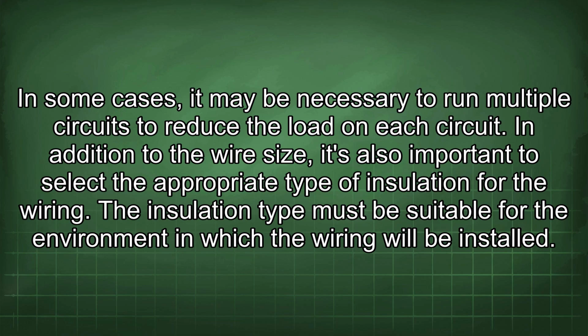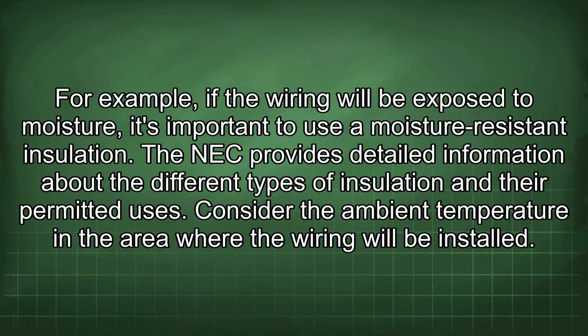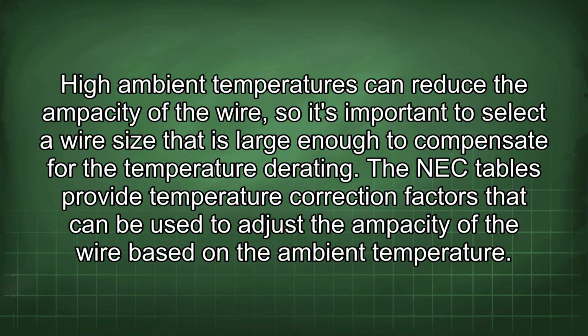The insulation type must be suitable for the environment in which the wiring will be installed. For example, if the wiring will be exposed to moisture, it's important to use a moisture-resistant insulation. The NEC provides detailed information about the different types of insulation and their permitted uses. Consider the ambient temperature in the area where the wiring will be installed. High ambient temperatures can reduce the ampacity of the wire, so it's important to select a wire size that is large enough to compensate for the temperature derating. The NEC tables provide temperature correction factors that can be used to adjust the ampacity of the wire based on the ambient temperature.